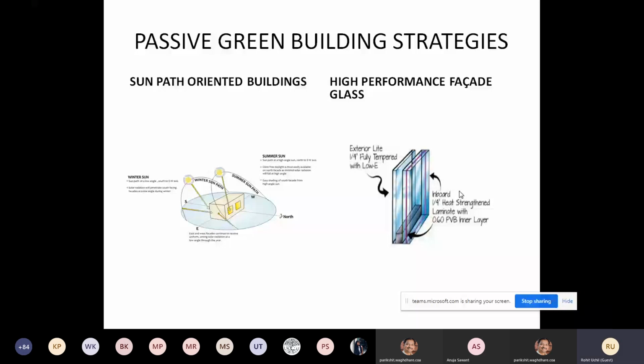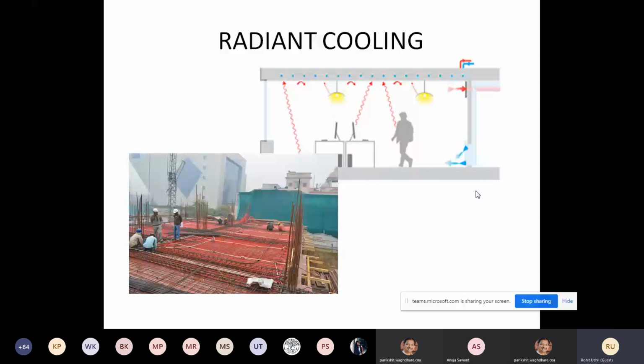I don't know if anybody has heard about radiant cooling. I'm sure you all would have studied it at some point of time, but I'll just give you an idea. It's the 20th century application of technology in buildings which was there many centuries ago. If you see old buildings and monuments, you will all notice that the wall thicknesses are huge. In some cases the walls are even 3 feet, 900 mm, or a meter thick, and this was to facilitate the storage of heat. So in winter, it would ensure that the space was warm, and in summer, it would ensure that the space was cool. So the radiant cooling system does the same thing using technology in a slab or a wall that might be 150 mm or 200 mm thick.